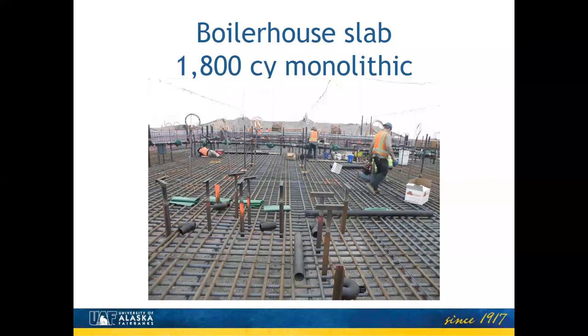The foundation supports the boiler house, and the boiler house has nearly 4 million pounds of load on it. That one is a large foundation. It's 5 feet thick, 85 feet wide and 115 feet long, and it consumes 1,800 yards of concrete. That was all placed in a single pour, and we had every batch plant in town supporting us on the deal. And maybe it's a construction guy thing, but one of the things I find fascinating about this foundation is that if you measure the neat line, just the volume of the forms on this, it comes up to be 2,200 cubic yards, but there's so much reinforcing steel in there that it displaced 400 yards of concrete. I was going to say that rebar is a good size rebar. Yeah, that's number 11 rebar. It's 1 3/8 in diameter. So, yeah, go ahead and throw one of those on each shoulder and have to work with it. Yeah.